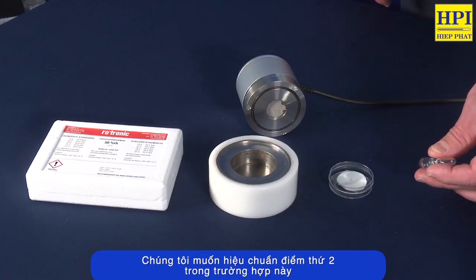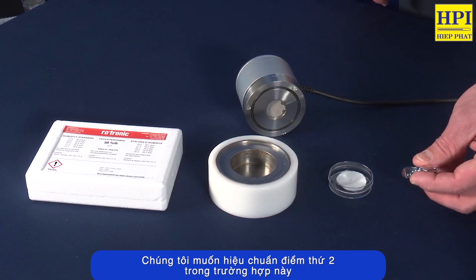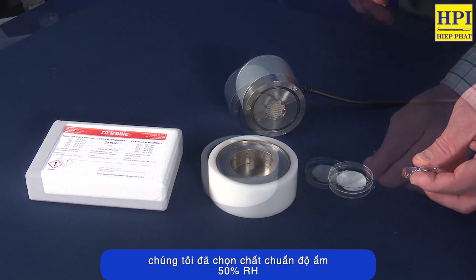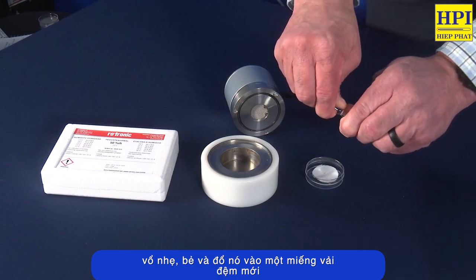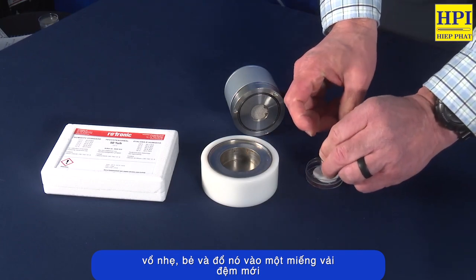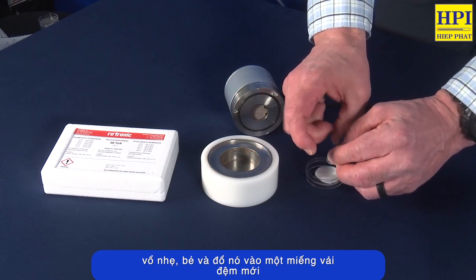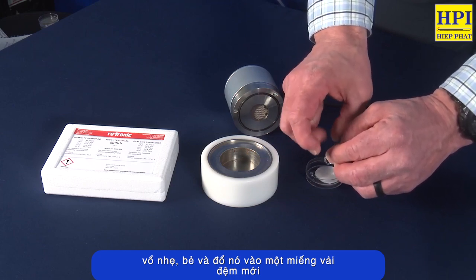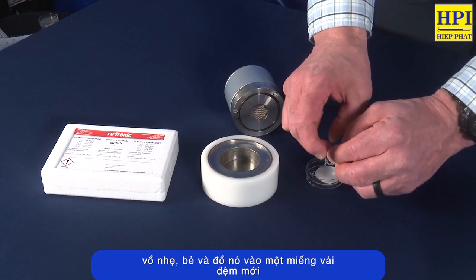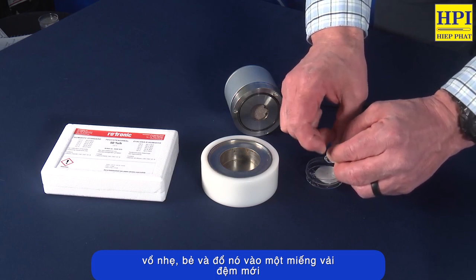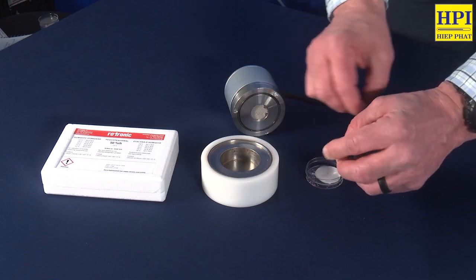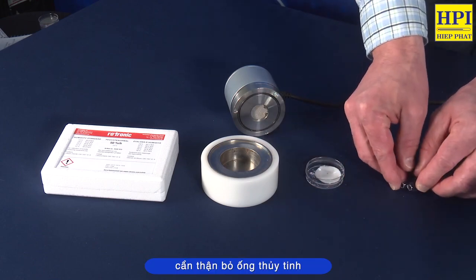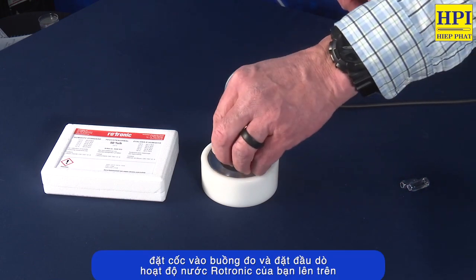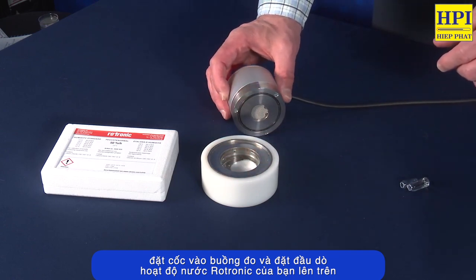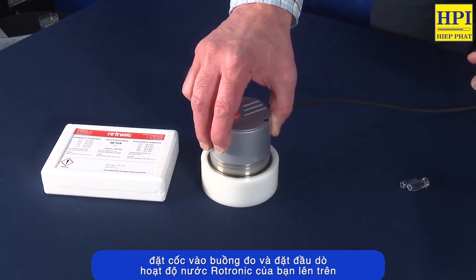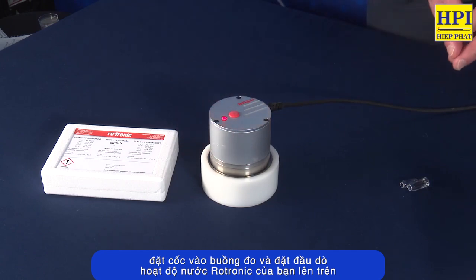So now we want to move to our second adjustment point. In this case, we've selected 50% RH. Again, tapping the vial, breaking carefully at the perforation, emptying the contents onto a new fiber disc pad. Carefully discard the glass ampule. Place the sample cup into the sample cup holder. And again, put your Rotronic water activity probe on top of the sample cup holder.